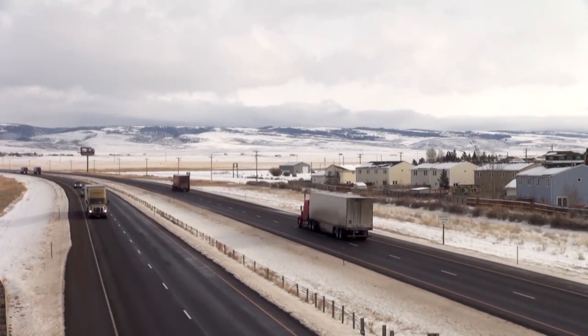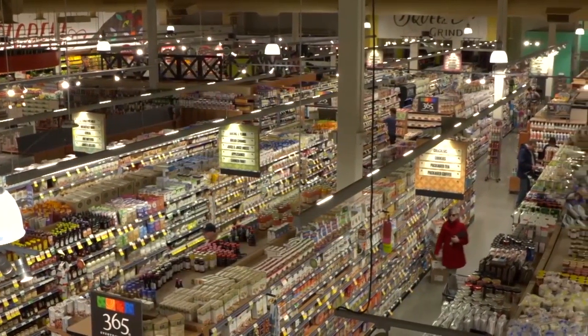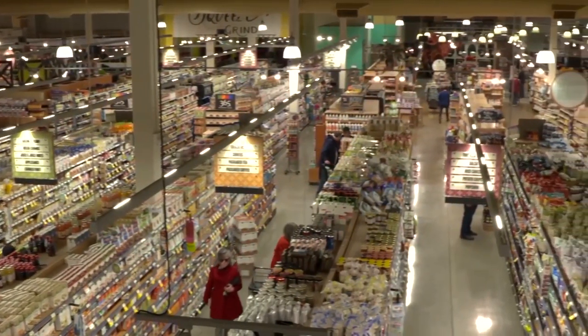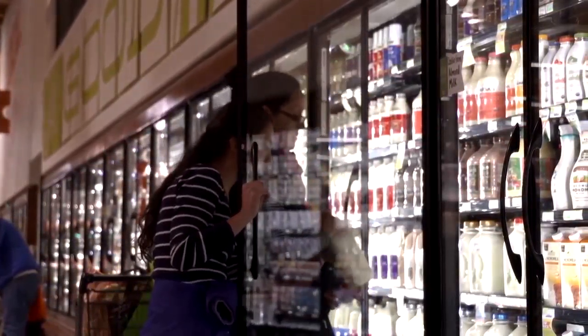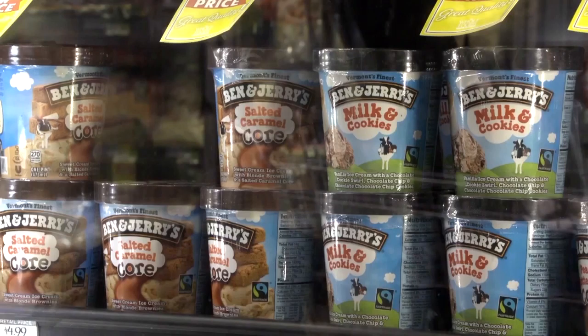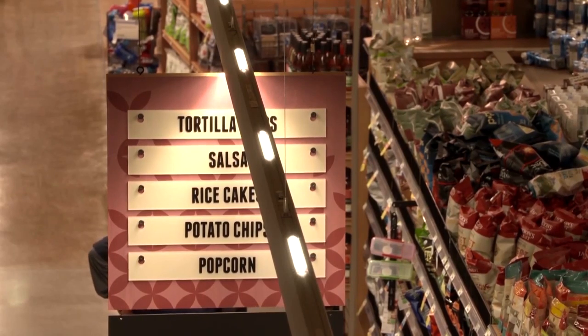Transportation accounts for less than 10% of all the energy used in the food chain. So what does actually consume a lot of energy? The store itself. One Whole Foods used 3 million kilowatt hours last year, equating to approximately $240,000 for one year of electrical usage. All systems compete with one another: HVAC competes with refrigeration, refrigeration competes with outside heat, and lighting varies by day versus night. The fridges and freezers that keep your salad fresh and ice cream cold really add up.